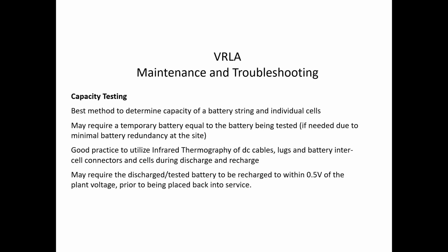Something you talked about, bringing a temporary battery out there. So if they don't want to cut service off, they want to make sure they have something. You bring out a temporary battery to replicate, and then you do your test, and then several hours after recharge, you can put it back in service. It's usually a 2-day process. We go in, temporary battery installed in parallel to everything while everything's hot. Then that battery's isolated. That's if it's a single string application.